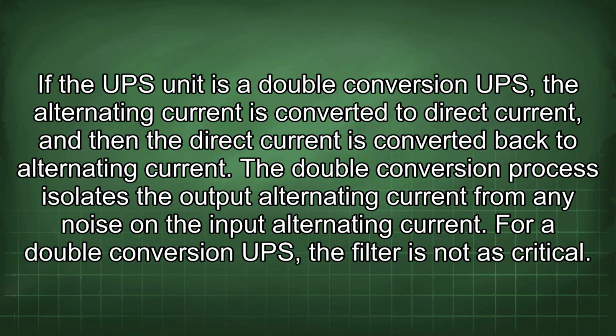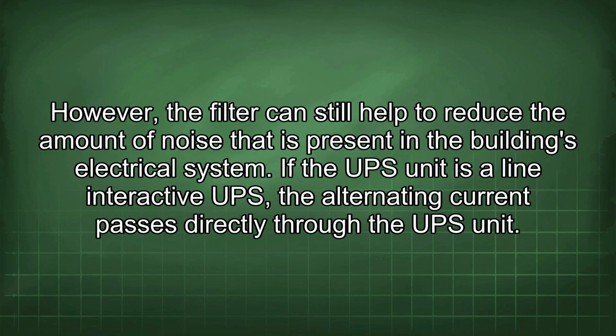If the UPS unit is a double conversion UPS, the alternating current is converted to direct current, and then the direct current is converted back to alternating current. The double conversion process isolates the output alternating current from any noise on the input alternating current. For a double conversion UPS, the filter is not as critical. However, the filter can still help to reduce the amount of noise that is present in the building's electrical system.